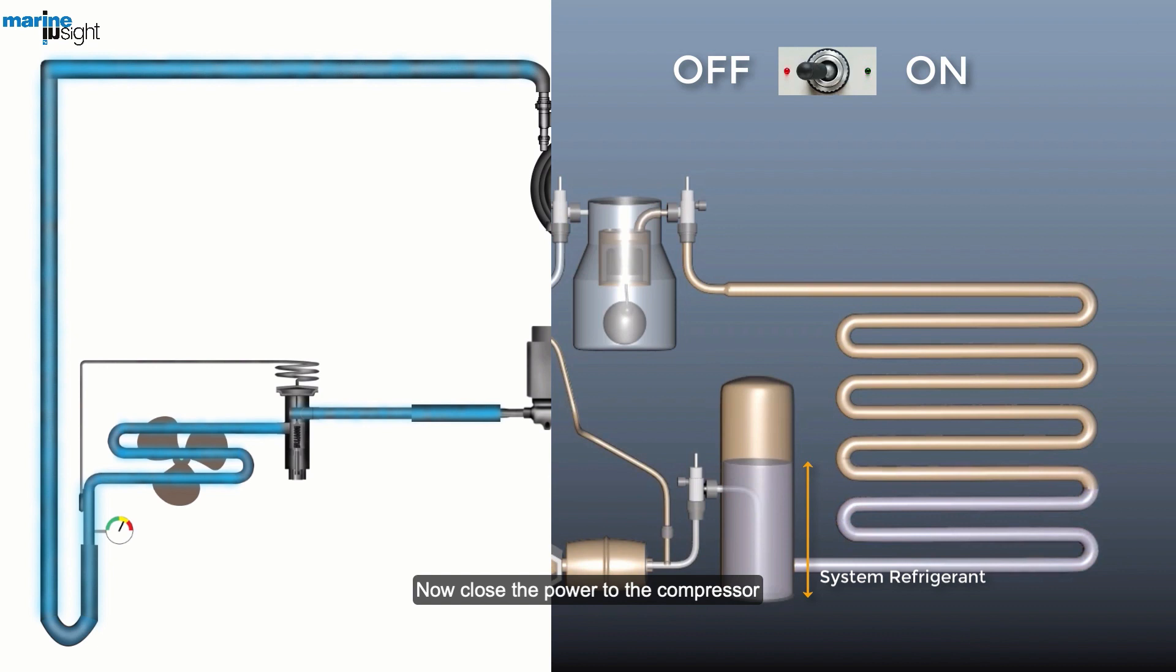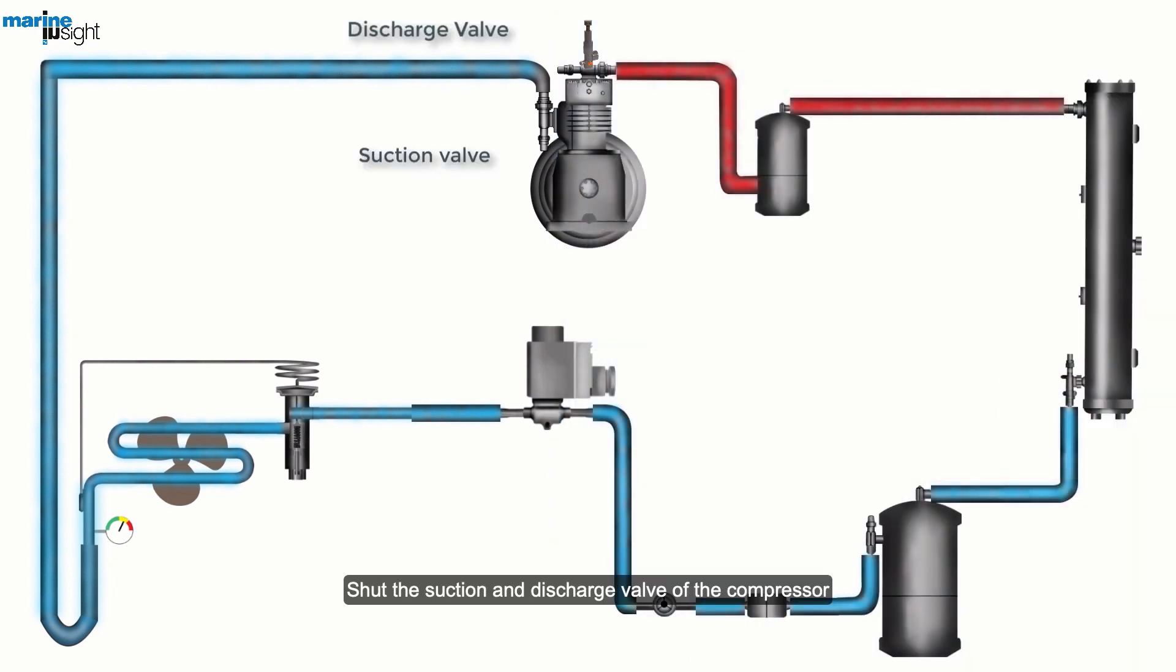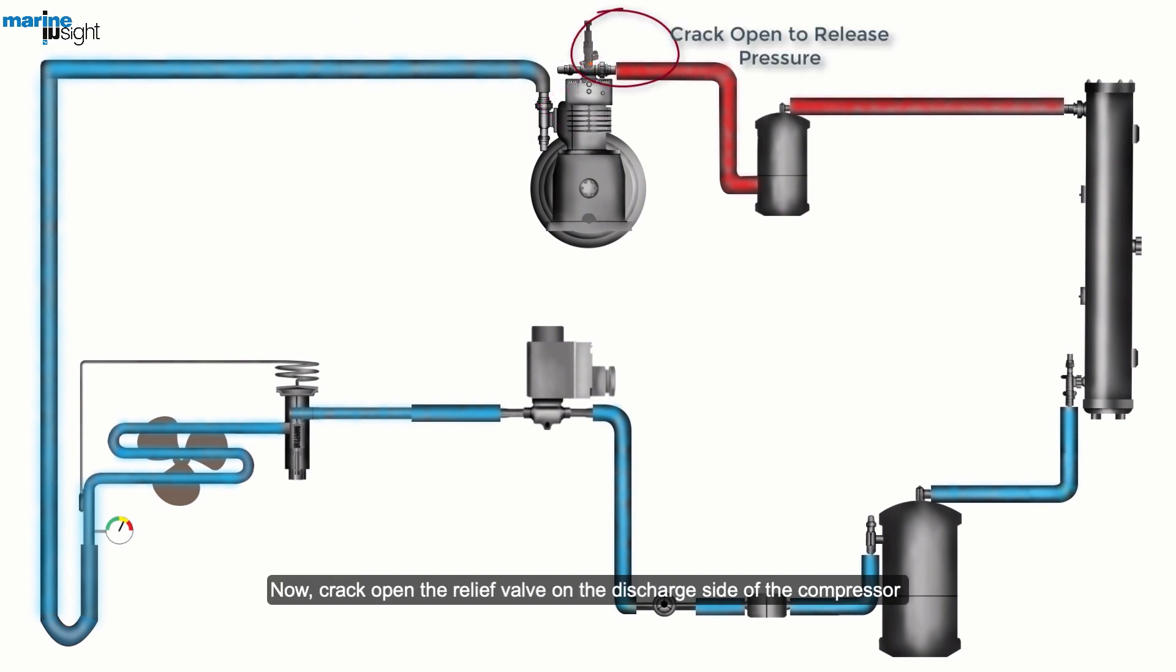Now close the power to the compressor. Shut the suction and discharge valves of the compressor. Now crack open the relief valve on the discharge side of the compressor to release any excess pressure, which will make it easy to charge the lube oil.